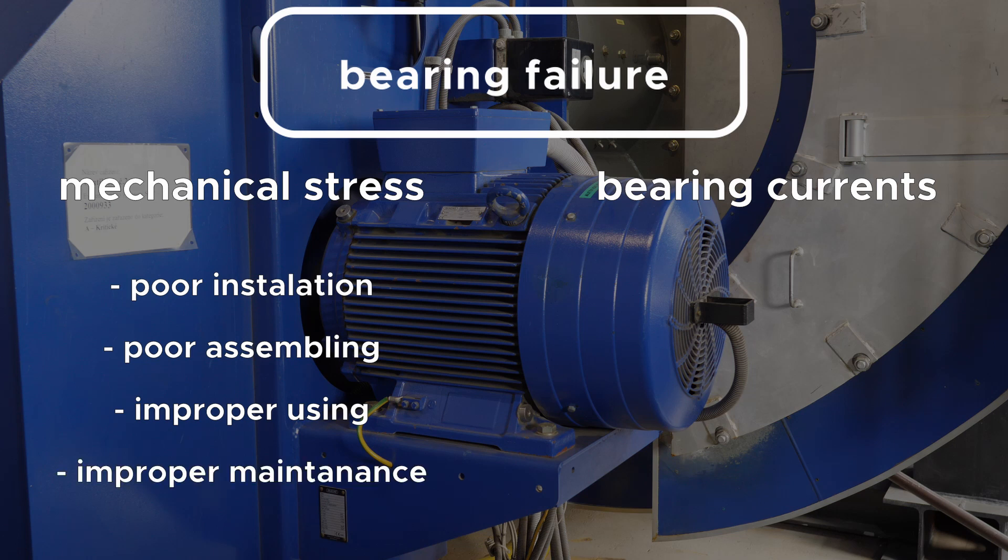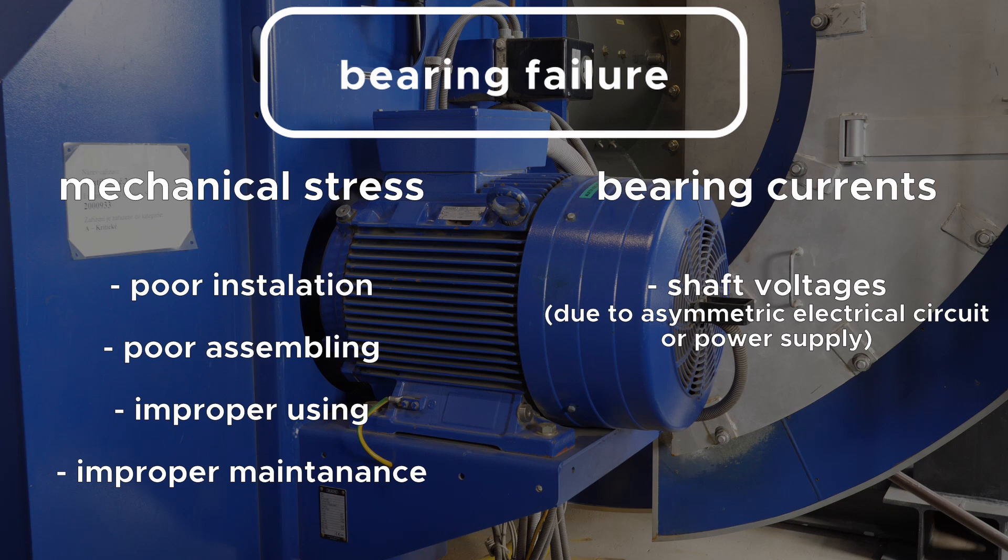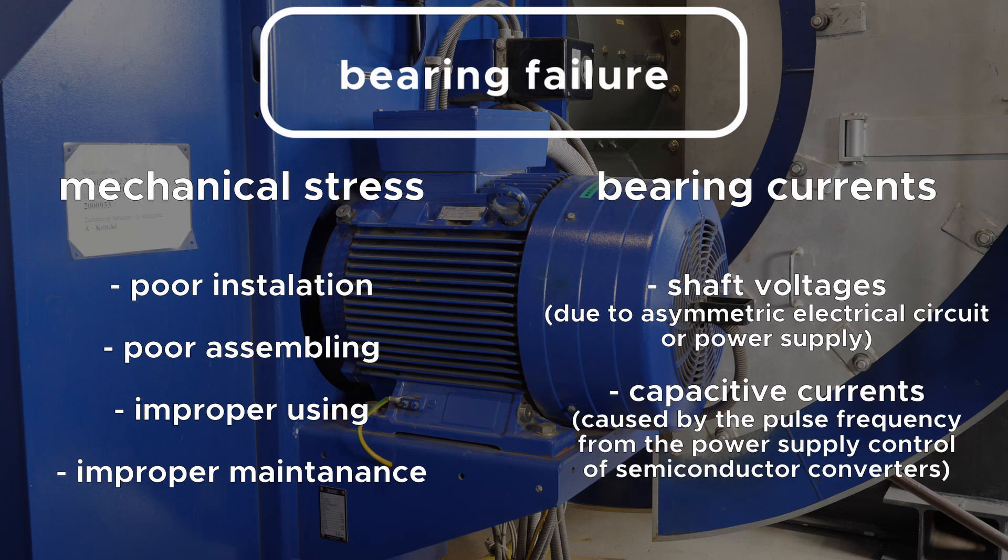The bearing currents can be caused by shaft voltages due to asymmetric electrical circuits or power supplies and capacitive currents caused by the pulse frequency from the power supply control of semiconductor converters.